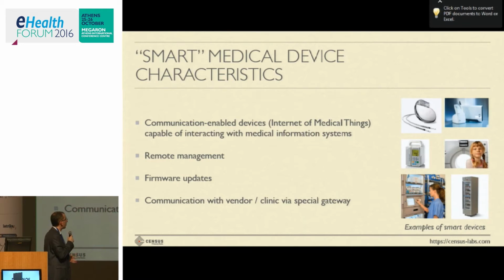So these are connected systems, often referred to as Internet of Medical Things. These systems offer remote management options, so you could remotely manage these systems in a way you could see what's going on in these systems. You could, for example, have the vendor provide a firmware update if there was a specific bug that this system had. And the way that vendors or other organizations talk to these critical systems is via special gateways, which are just like black boxes that these medical devices use to communicate with the vendor. So the vendor uses this black box to issue a firmware upgrade or whatever software upgrade to these systems, so that this happens in a controlled manner.